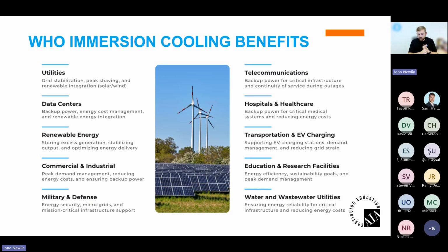We typically say critical infrastructure and densely populated areas is where you see pushback happen from communities or AHJs, or where you're near high-risk environments where we don't want to lose property or personnel. That's where immersion cooling on the safety side might be emphasized. On the other hand, you might be out in the middle of the desert where we don't necessarily care about fire risk, though we still have better heat transfer and better performance with immersion cooling. We could get better ROI off systems that might be front of the meter, doing arbitrage, frequency regulation, whatever those deployments might be. So this impacts a lot, from the fire safety side in critical infrastructure and dense populated areas, to the performance side at large scale.